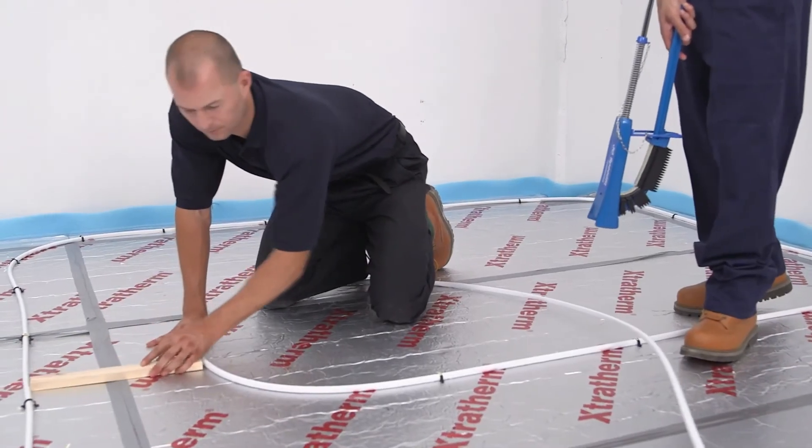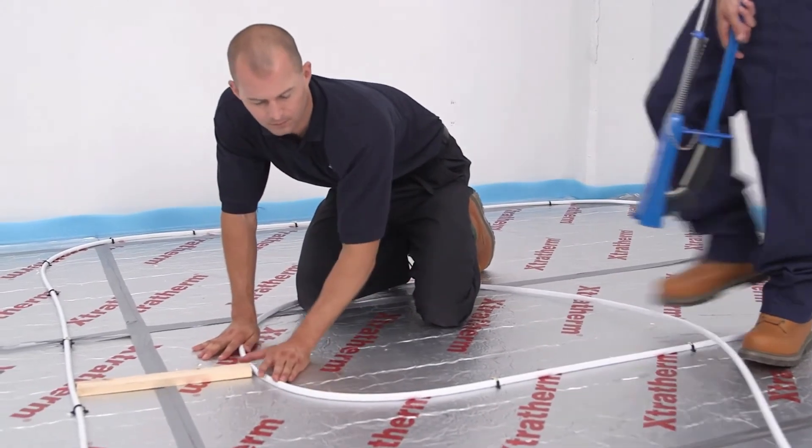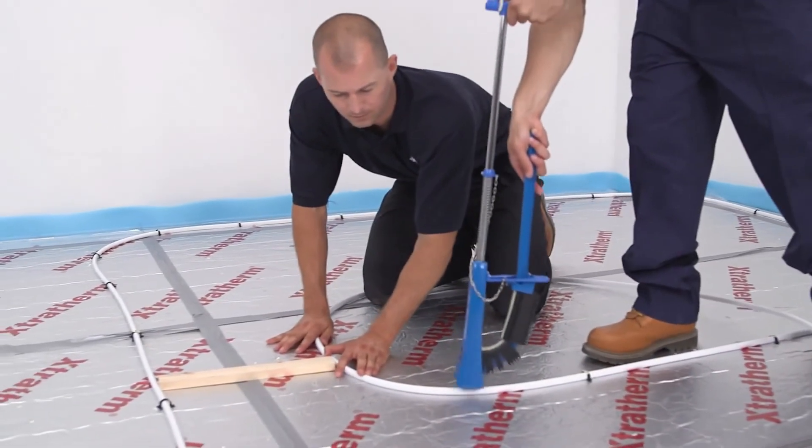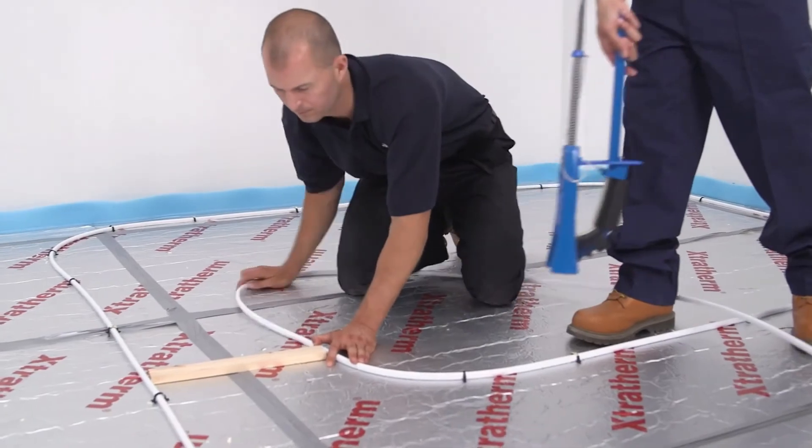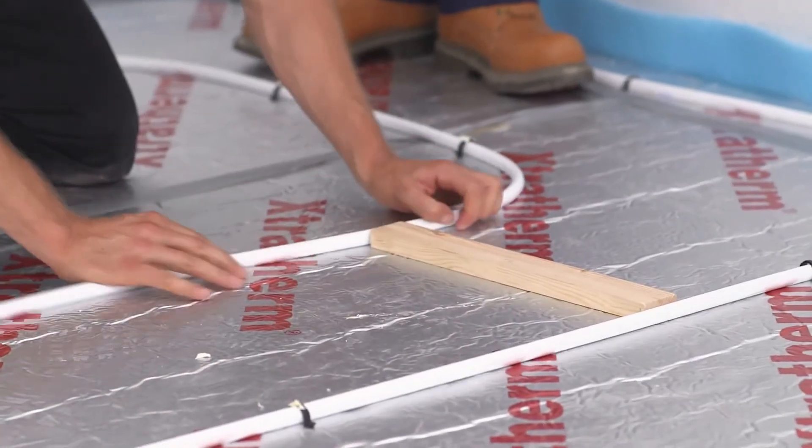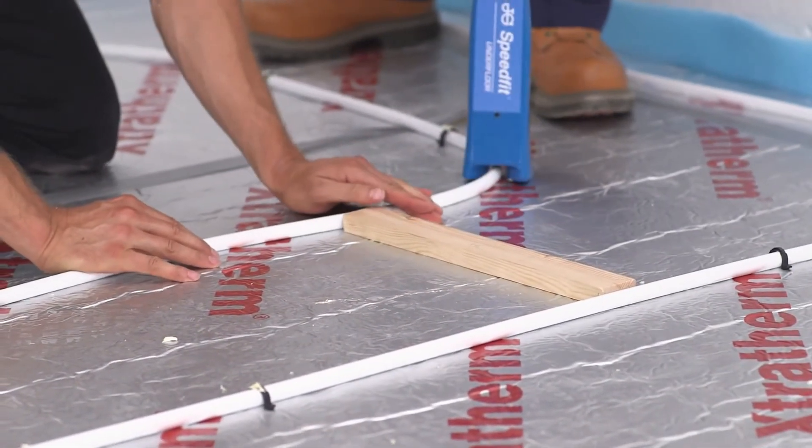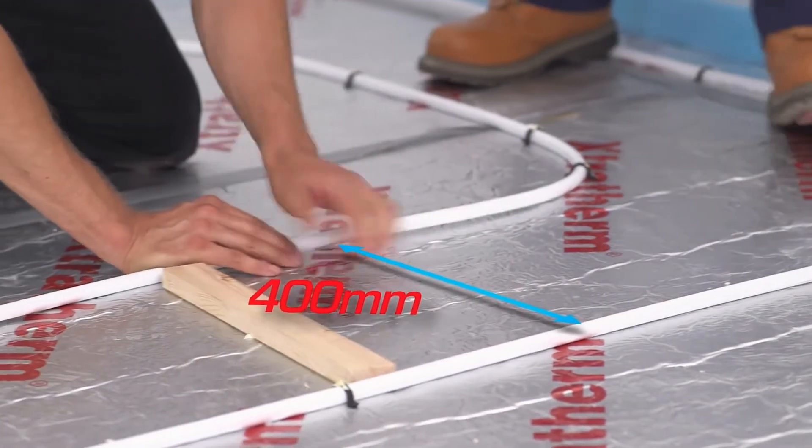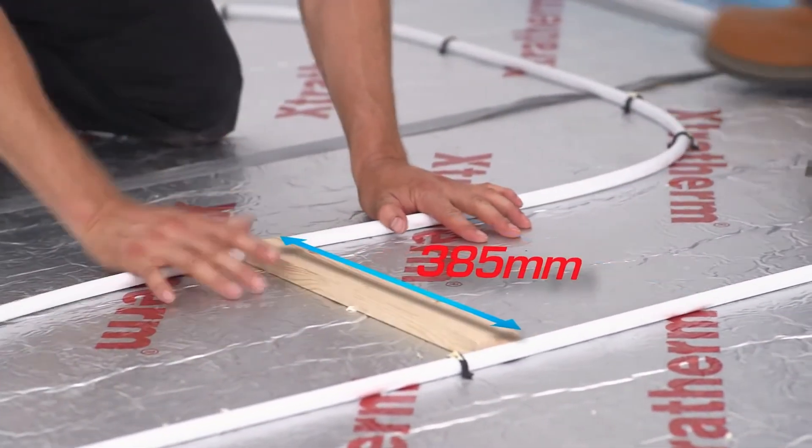Take care to keep the correct distance between pipe centres. The use of a spacer batten placed between the pipes will help here. Because the pipes are 15mm in diameter, subtracting this amount from the centres will give you the length of the spacer to be cut.